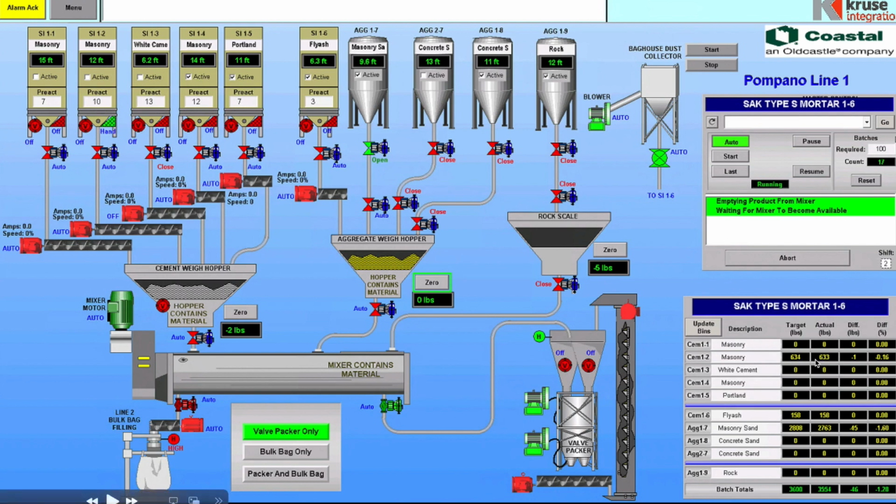If it's out of limits, it will pause and let you know, and therefore you can pause the system, and you can manually add more weights from the other products to make it equal, so you don't have to ruin the batch. And then there is also the total weight that's in the recipe, so it wants to see what the comparison is. And all of this data is recorded in your database for each batch.